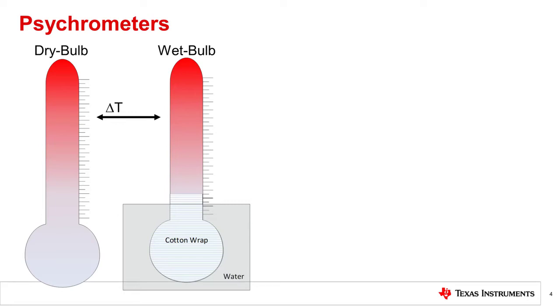One drawback of this style of humidity sensor is that because the wet bulb thermometer is relying on evaporative cooling, external environmental factors such as the atmospheric pressure can cause inconsistent readings. It is also true that if two thermometers have an accuracy difference to begin with, that will show up as an error in their final RH measurement after conversion. Assuming those parameters are well controlled for, knowing each of these temperatures can allow us to find the relative humidity, absolute humidity, or by extension any other psychrometric value by using the psychrometric chart.